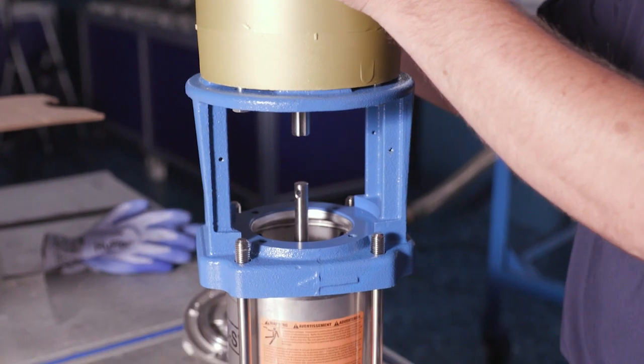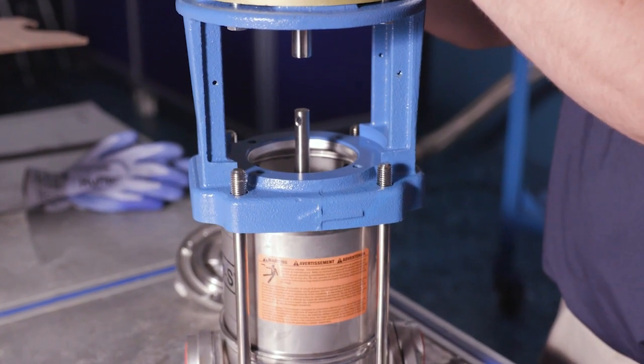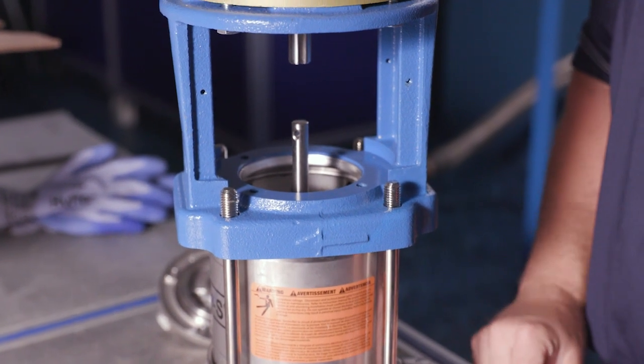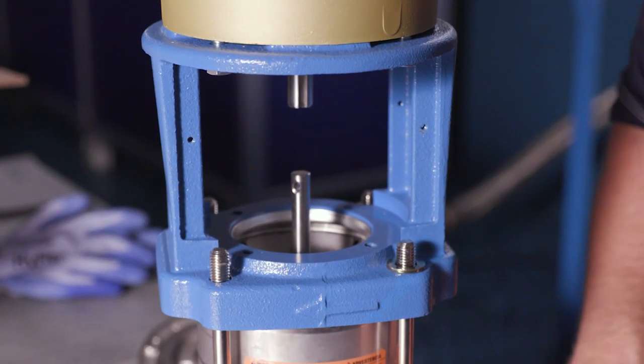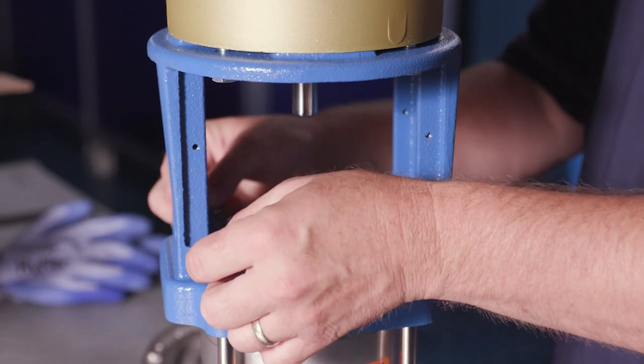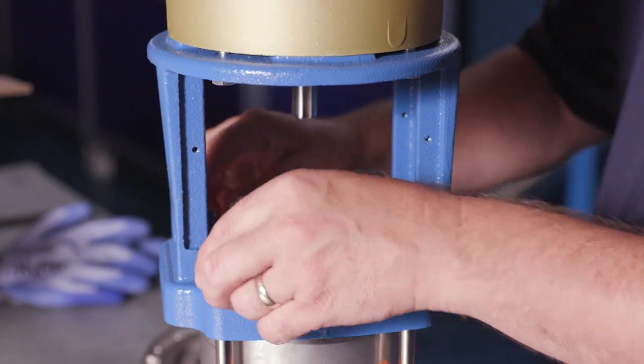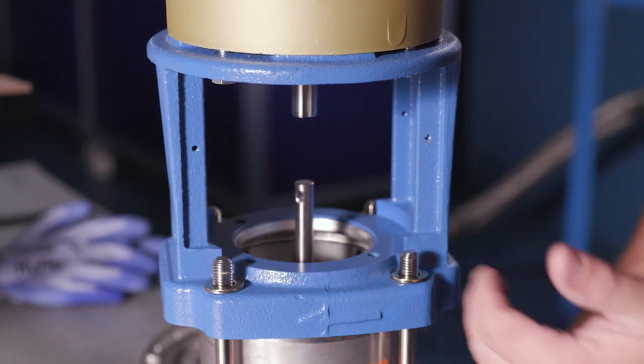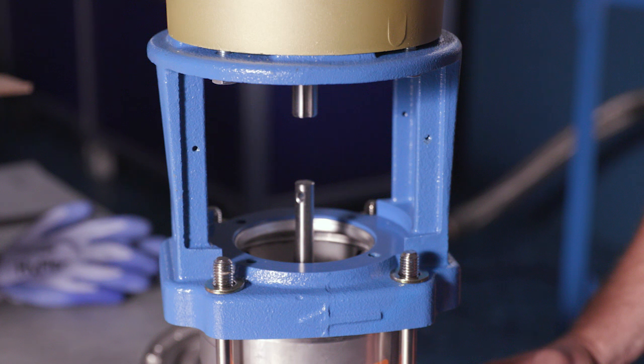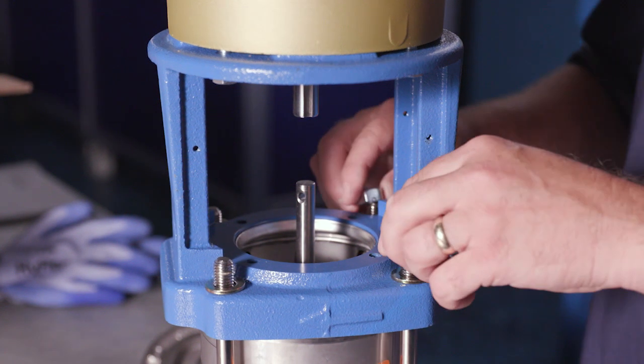You've got to line up your four bolts, and from that point we've got to put our washers and our nuts and we want to tighten those up evenly. There is a torque spec in the book. We want to look at that. We also want to do the star pattern. Tighten those nuts up evenly and to the torque spec in the book.